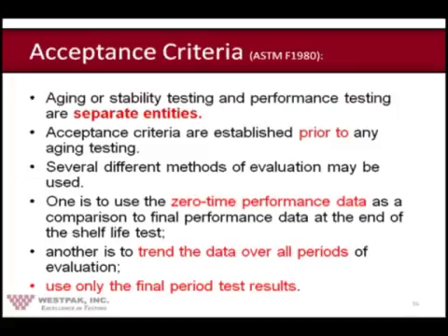So even though it's obvious to the casual observer, it's likely that some confusion existed early on, requiring that the writers of the standard include a note like that. It's also interesting to note that the standard requires establishing acceptance criteria prior to conducting the aging test. Once aging results are obtained, they should be compared to the zero-time performance data for the package.